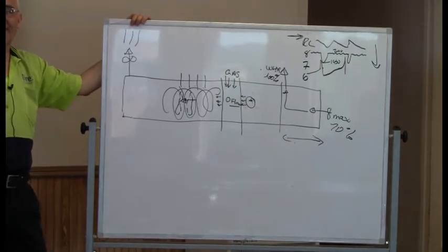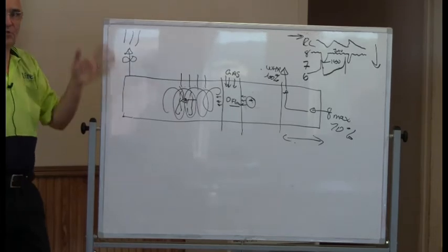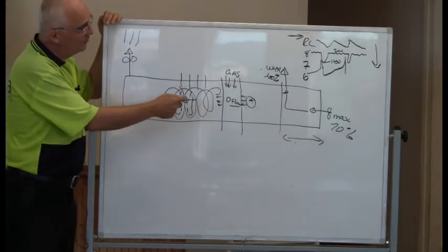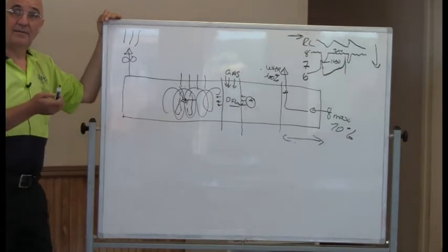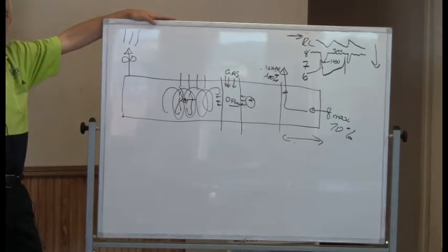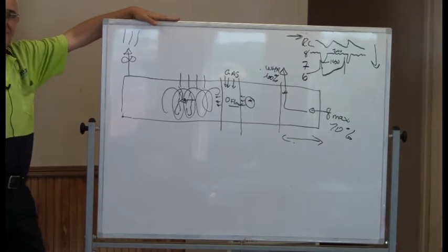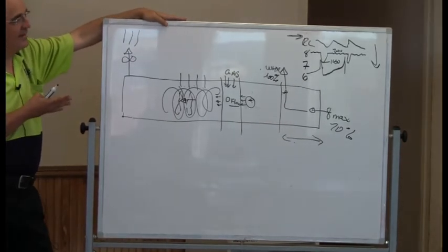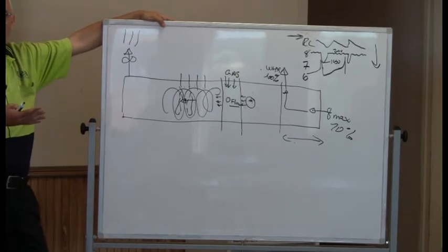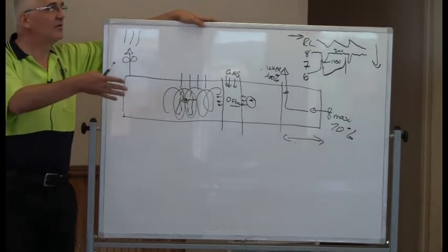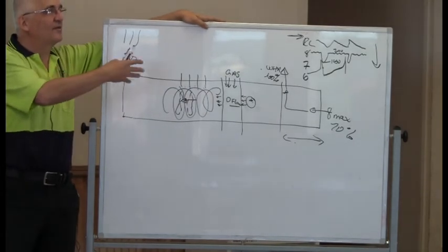Even though you are blowing air, you are actually creating a torch. That contributes to burning the smoke, and actually you save energy when you flash, because you basically introduce energy during that period without excess air through the firing zone.